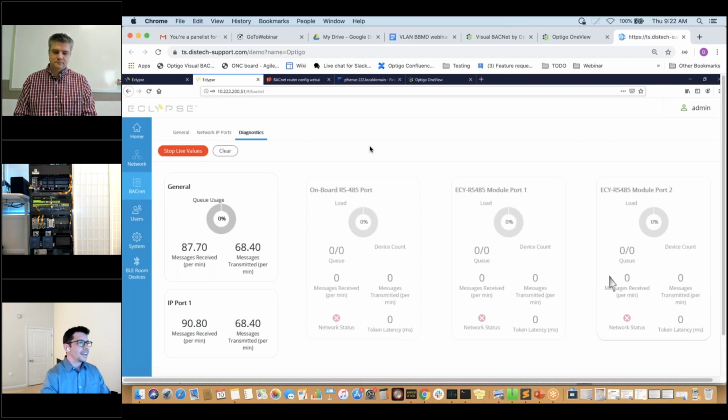And then on top of that, they're going to turn it into a BBMD and just add one more job onto it, plus graphics and everything else. And it can handle that, but as you keep adding those things, it's becoming a bigger and bigger single point of failure. So ultimately, on a large network, I would always have one device. If I need a BBMD, I'm just going to add one small device and have it do that job, and that's its job, because it's critical to the network.